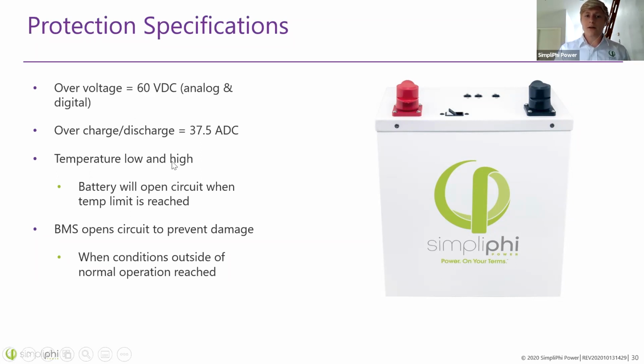It's also going to handle temperature, low and high. So if the inverter tries charging the batteries at low temperatures, the battery is going to open the circuit or reduce the amount of current going into the battery. So this temperature protection is actually handled inside of the battery itself. So even if you needed temperature protection with a different inverter other than the Solarc, that's still possible.